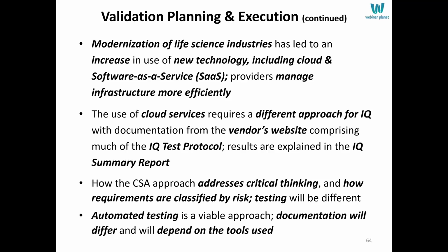And what you do is you create a protocol that says, I'm going to go to the vendor's website. I'm going to look at all their policies, procedures, practices, and certifications, and gather all those links and information. And then in my report, I'm going to indicate whether or not they are qualified to do this job. It's something that FDA has not come out and said that's the way to do it, because they're not going to tell you how to do it. But if you use cloud services or software as a service, you have to be able to qualify them some way. And this seems to me to be the most obvious way to do that.